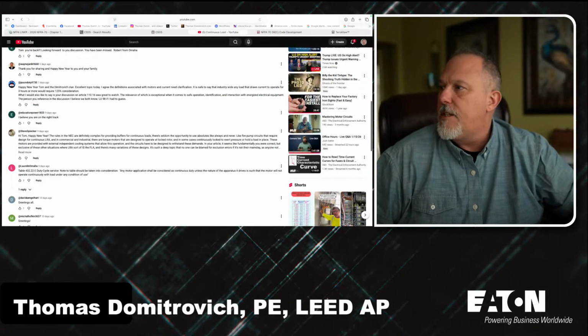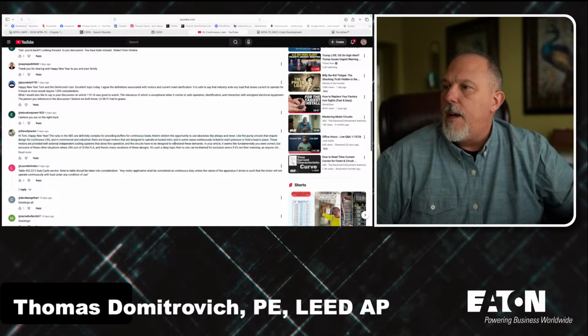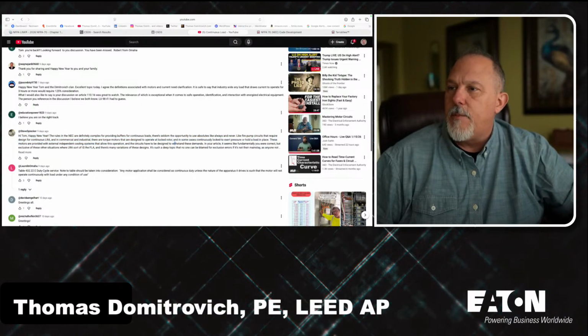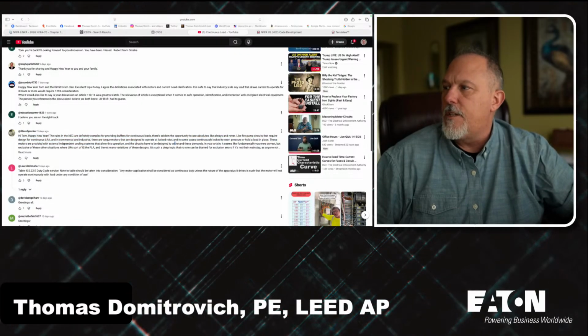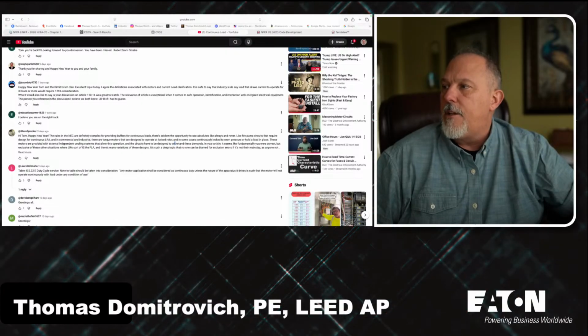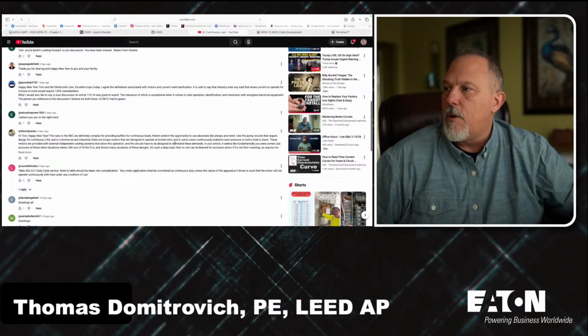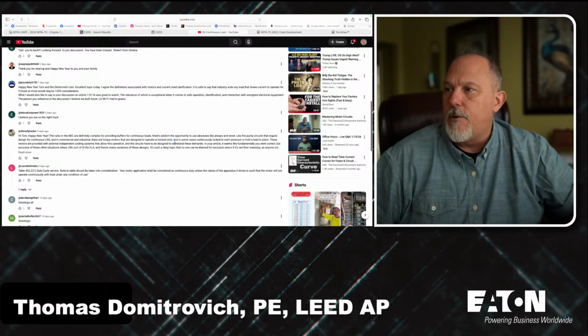I'm reading right here, Steve - there's your comment: absolutes like always and never, like fire pump circuits that require design for continuous locked rotor amps. And in commercial and industrial settings, there are torque motors that are designed to operate at locked rotor.